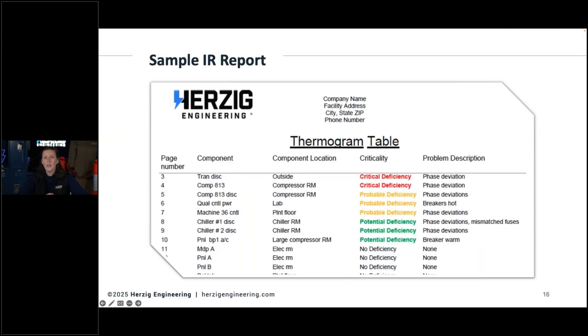Understanding what condition the equipment is in can be hard to figure out right off the bat. Having an infrared inspection can help determine that. Yes, you have to do them every year just to make sure everything's still going, but if you don't have a clear starting place for your maintenance plan, you can use an infrared inspection to help prioritize things. If there's a critical deficiency, a serious hotspot identified in your thermography report, that's your first priority. That's where you get started, and then you go back and check on them later. The ones with little to no deficiency, running as normal, should still be included in your maintenance plan, but if you need to figure out a priority list, this is a good way to do it.